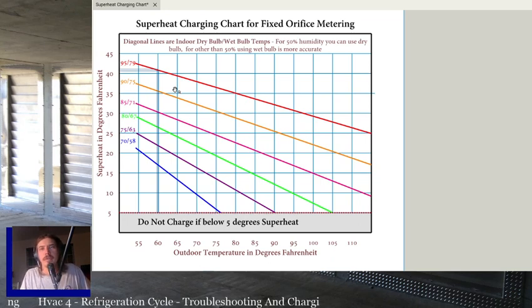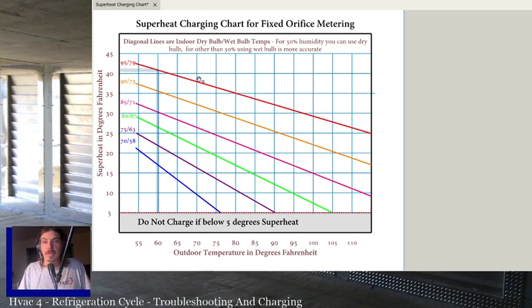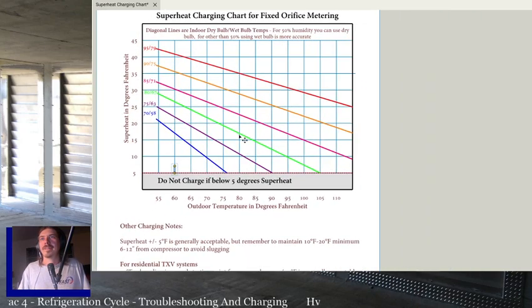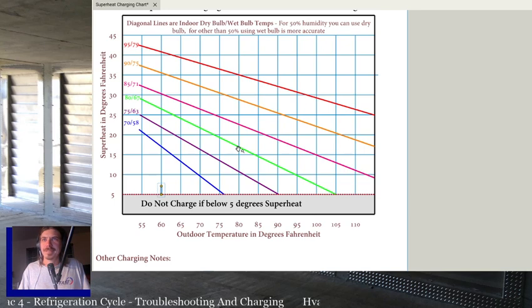Anytime your indoor temperature is high, you're obviously going to have high superheat because you've got to pick up a lot of heat. The more heat you have to pick up, the higher the superheat's going to be. So basically, those two things combine to create a very high superheat condition. And seriously, it's not uncommon, even at 70 degrees outside and 90 degrees inside, to see 40, 45 degrees of superheat, and the charge is pretty dang close. The reason I bring it up is, like I said, guys will see something over 20, 25 degrees of superheat, and that's when they start freaking out. Because it's like, what the hell is going on? Why is the superheat over 30 degrees? That doesn't make any sense. Well, it might make sense. You've got to pay attention to the conditions where it does make sense.